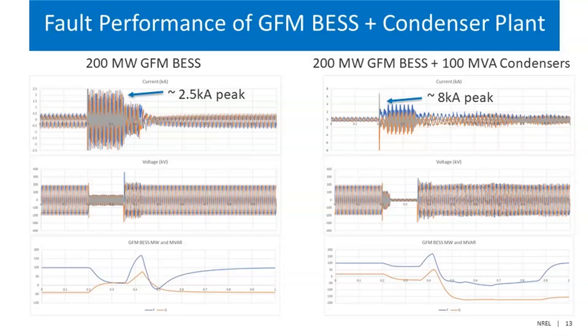So, again, you need to look at this problem from both sides. You provide short-circuit current, but at the same time, your synchronization back to the grid might be delayed because of the high level of transients.